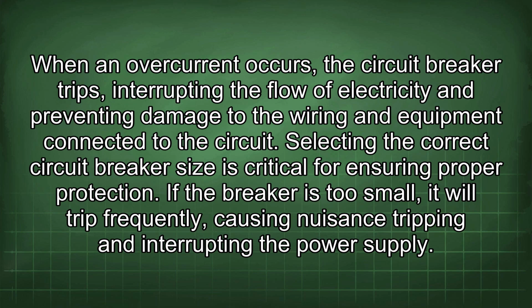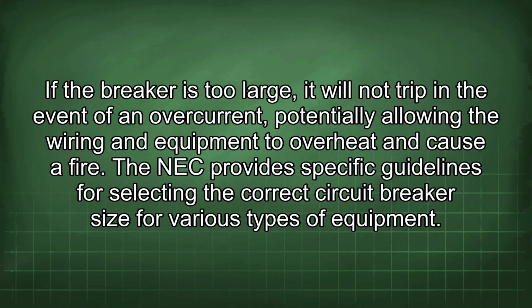If the breaker is too small, it will trip frequently, causing nuisance tripping and interrupting the power supply. If the breaker is too large, it will not trip in the event of an overcurrent, potentially allowing the wiring and equipment to overheat and cause a fire. The NEC provides specific guidelines for selecting the correct circuit breaker size for various types of equipment.